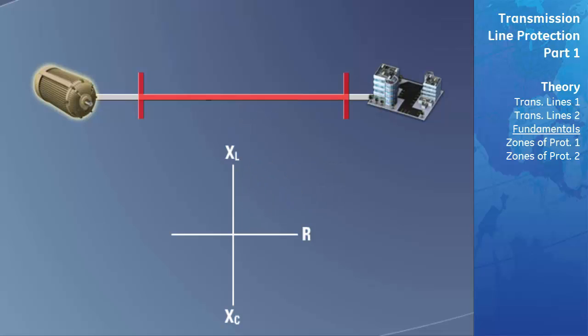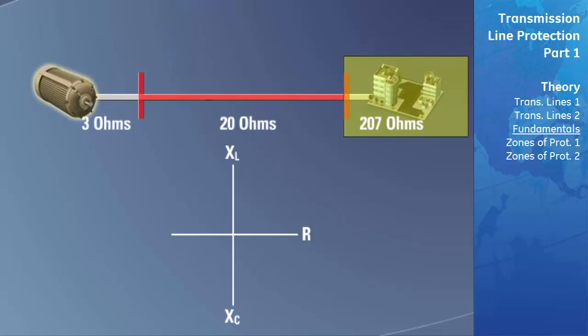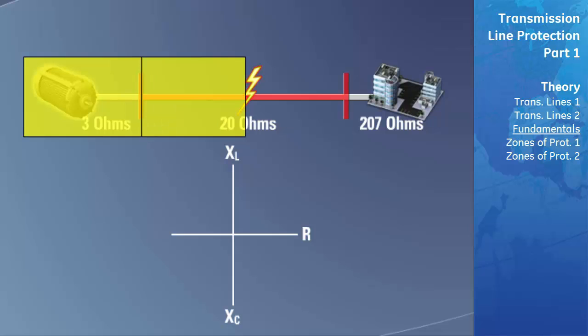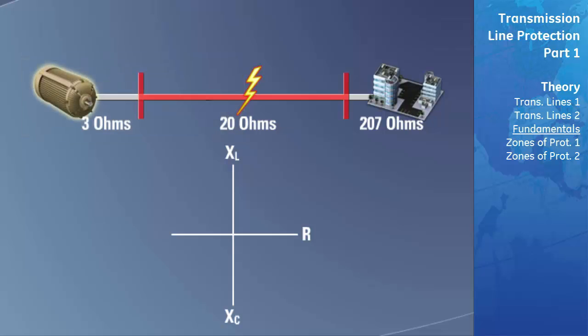In a normal power system, there is a load at the end of the transmission line. Typically, this load is mostly resistive and is also larger than all of the other impedances of the power system. Therefore, if you were to plot the impedance of a power system under normal conditions on an RX diagram, the point would be shown very close to the x-axis. The distance from the origin would be the magnitude of impedance of the transmission line and the load. If a fault to the ground were to now occur at the midpoint on the transmission line, all of the impedances after the point of fault would no longer be part of the power system. The impedance of the system would now only be the impedance of the source plus the impedance of the part of the transmission line before the fault. Since the power system impedance is no longer mostly resistive because the only impedance is now the transmission line which is mostly inductive, the plotting of the measured impedance on the RX diagram will be very close to the y-axis. The impedance point will actually fall along the line drawn from the origin to the impedance of the entire transmission line.